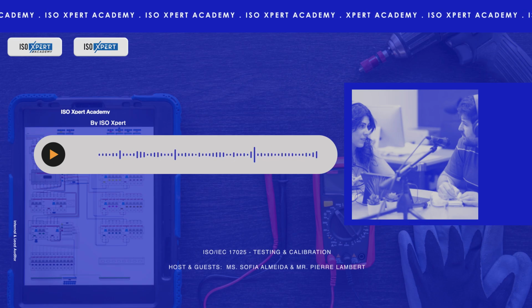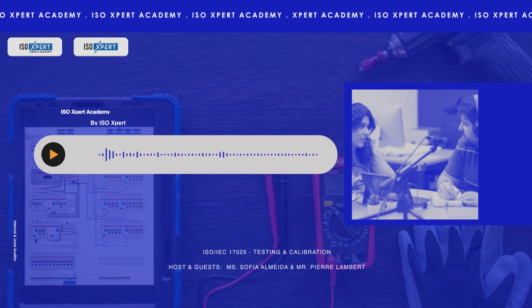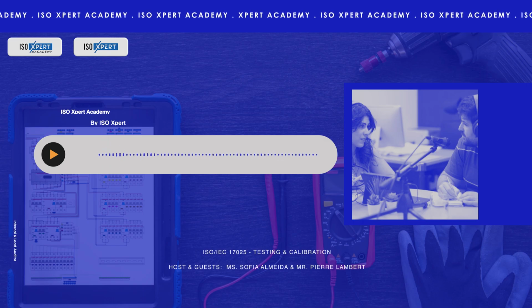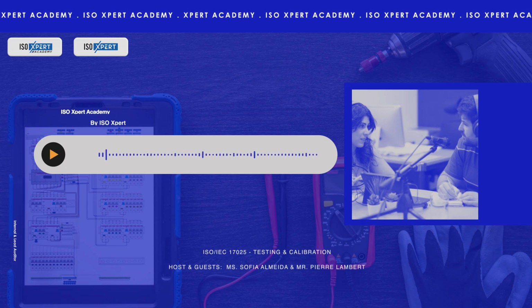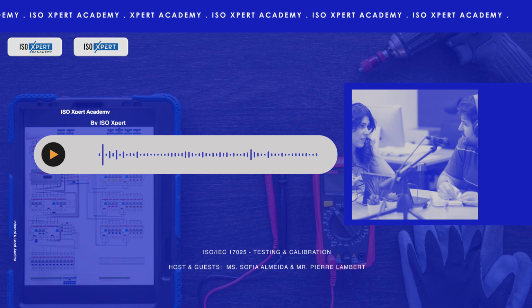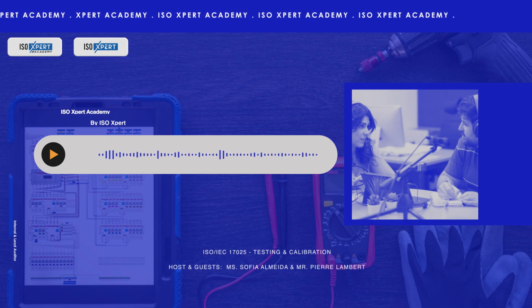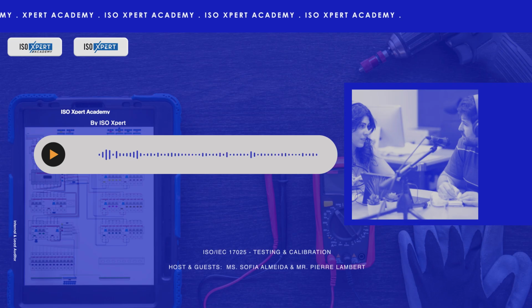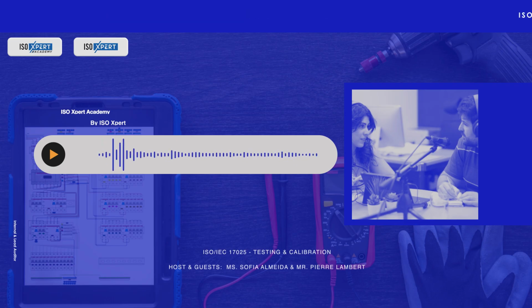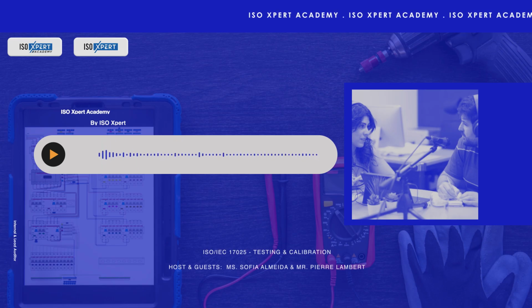So improvement is the goal, but what happens when things do go wrong? We touched on non-conforming work, but 8.7, corrective actions, seems more focused on fixing the underlying cause. Precisely. Non-conforming work deals with the immediate problem. Corrective action deals with the root cause to prevent it from happening again. When a nonconformity is identified, maybe through an audit, a complaint, or internal QC, the lab needs a process to investigate why it happened. Auditors review corrective action reports, CARs. They look for a thorough root cause analysis, not just blaming an individual, but looking at systemic issues.